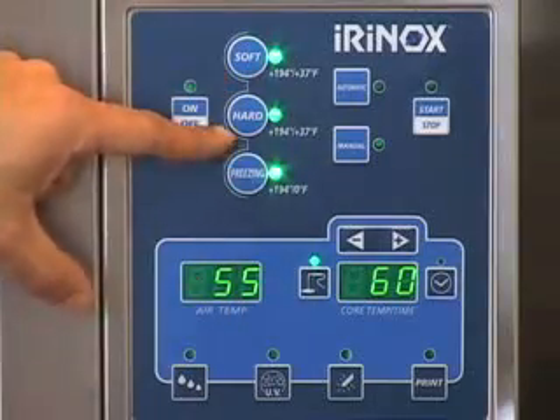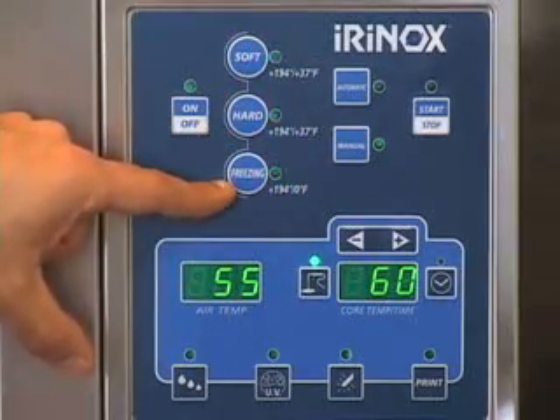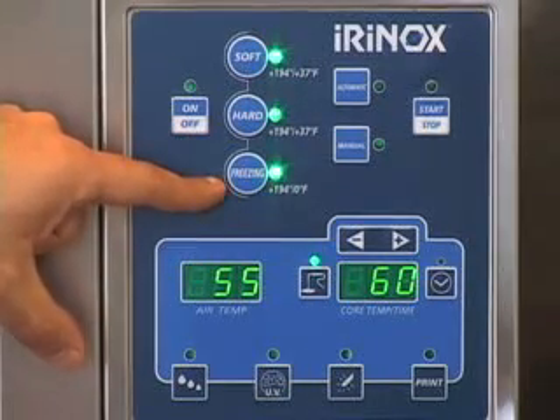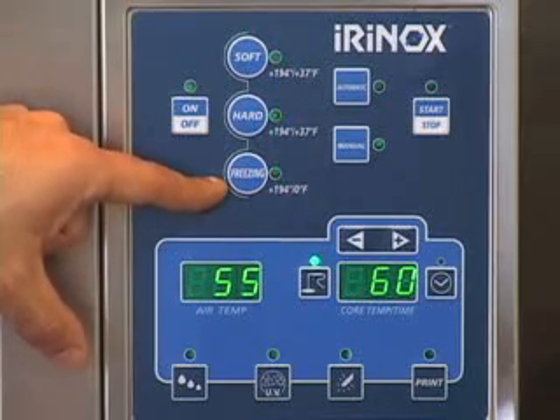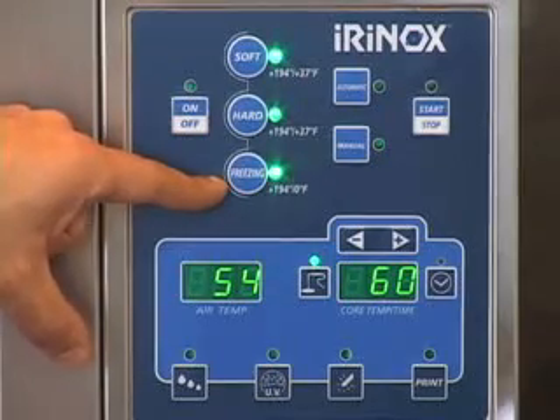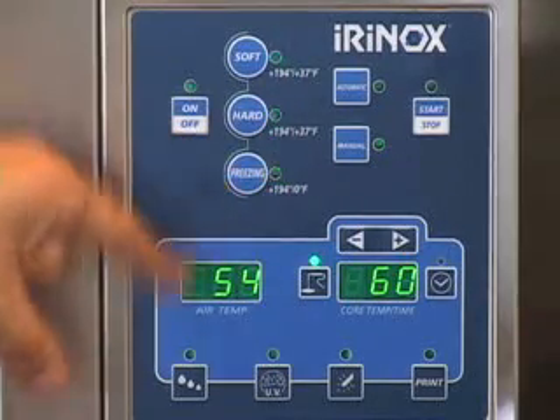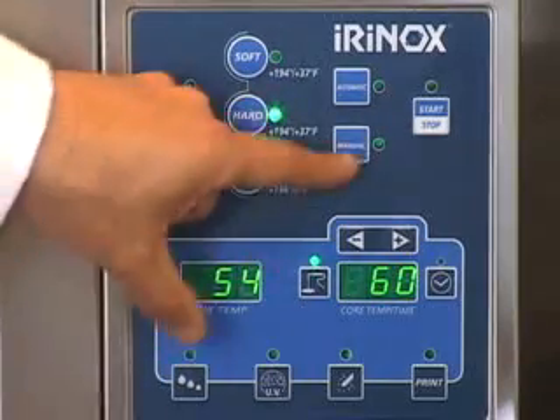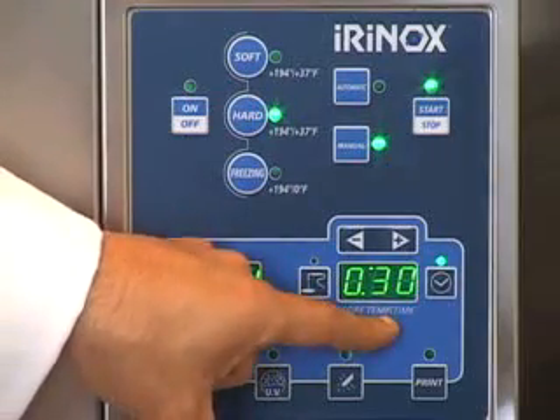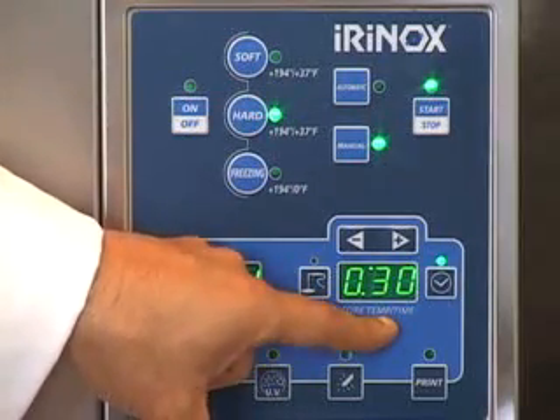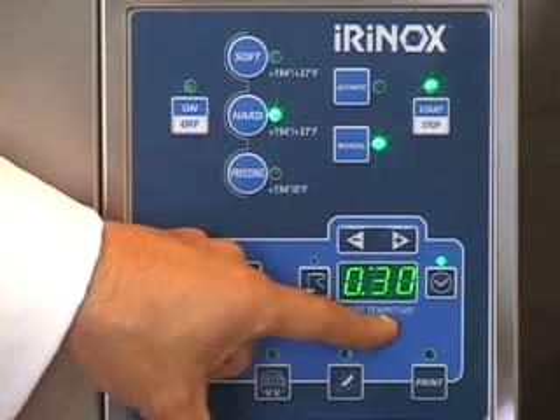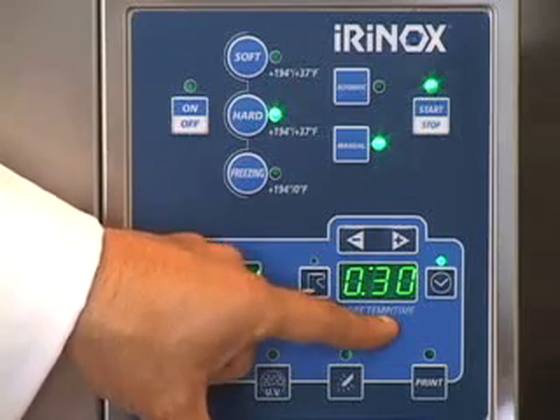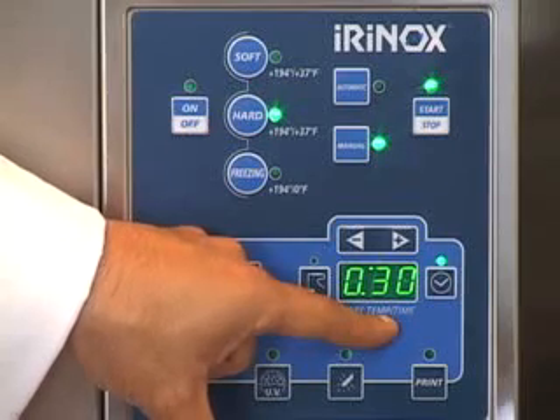Whether you select soft, hard, or shock freeze mode, it's important to remember that the machine is going to run strictly for a period of time and then go to hold mode, irregardless of the temperature at the core of the product. So it's something that you need to confirm the food is at the proper temperature prior to removing it from the chiller. For example, if I hit hard and then manual and start, the machine is going to run for 30 minutes at -4 degrees Fahrenheit, and then for 60 minutes between 30 and 34 degrees Fahrenheit, or the soft chill mode.